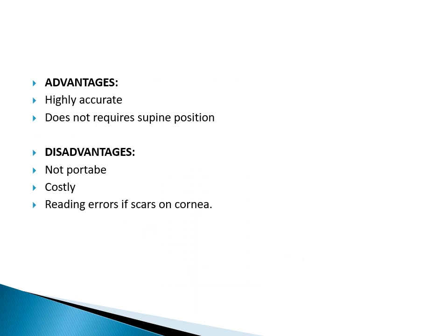The Goldmann applanation tonometer is highly accurate and does not require a supine position. While the disadvantages are: it is non-portable, it is costly, and reading errors are seen if there is a scar on the cornea.